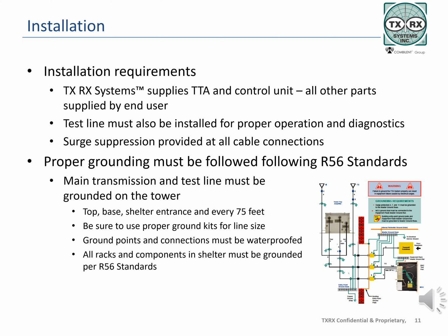All sites should be grounded to R56 standards inside the shelter. Transmission lines can develop a charge on the outer insulation or jacket on the tower from wind, resulting in static discharge. All main lines and test lines must be grounded on the tower, at the top near the antenna, at the base of the tower, at the entry plate to the shelter, and depending on tower height, every 75 feet. Ground kits are sized to the feed line, so be sure to get the right ones. After installing the ground kits, they must be waterproofed.